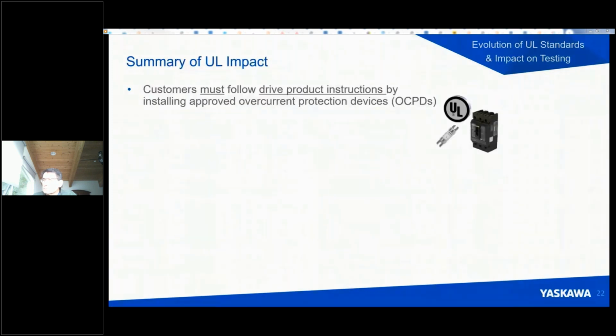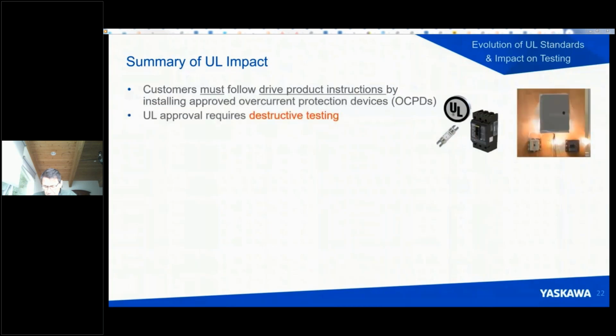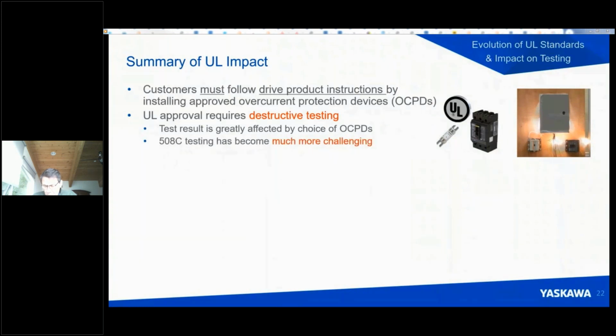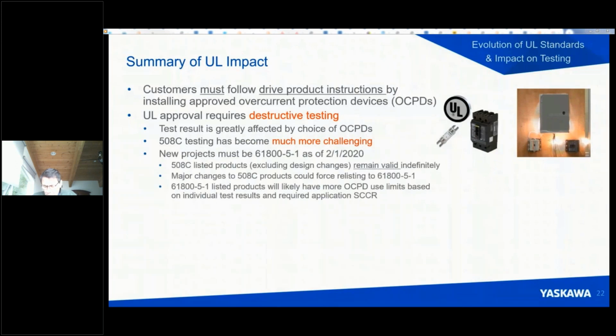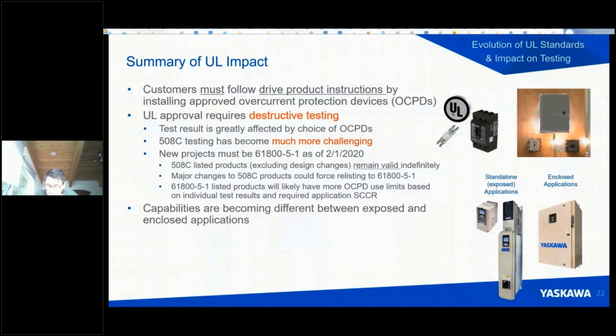So let's talk about the summary of the UL impact. Customers must follow the drive product instructions as we just mentioned when using these devices to protect a drive. And UL requires that the manufacturers do destructive testing. The test result is greatly affected by the choice of these devices. Again, 508C has become much more challenging. New projects have to use the new standard going forward. And then capabilities are becoming different between exposed and enclosed applications. So this again is just a summary of what we just discussed with regards to the UL standards.